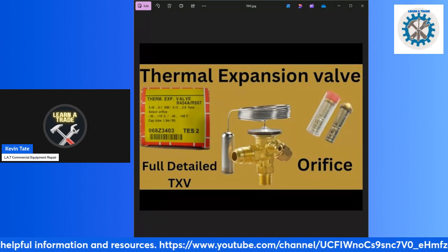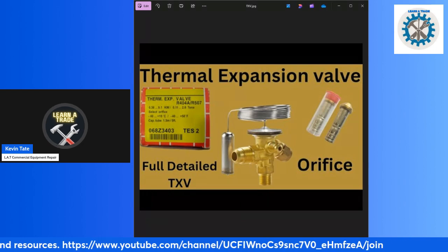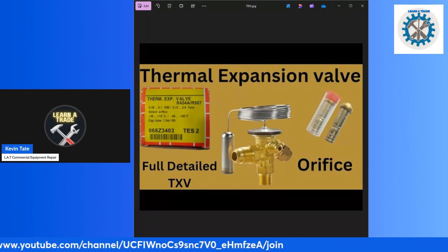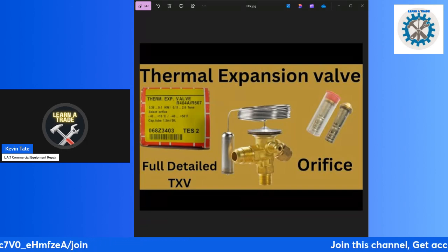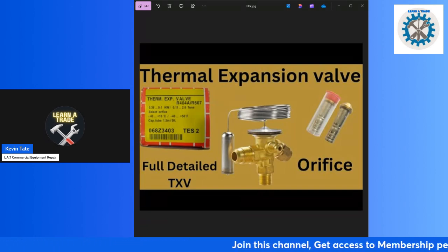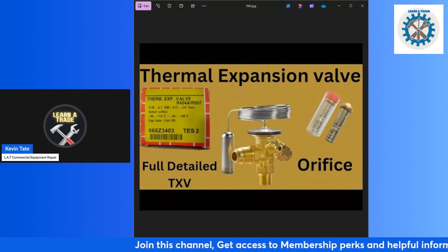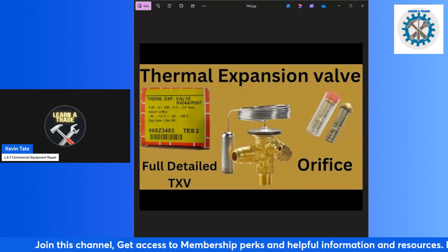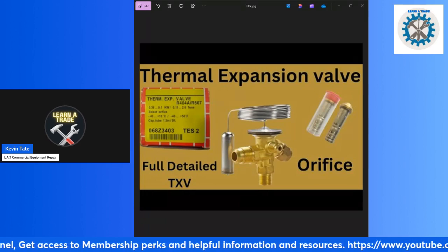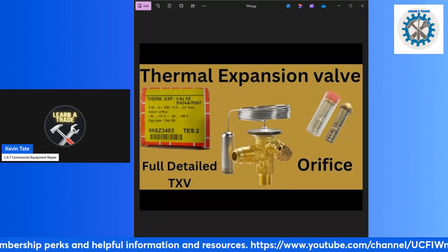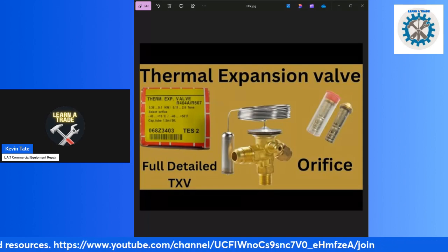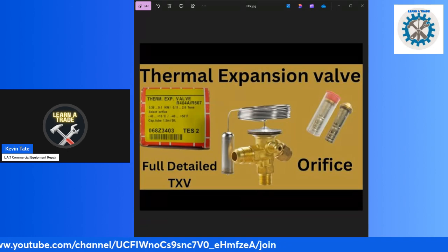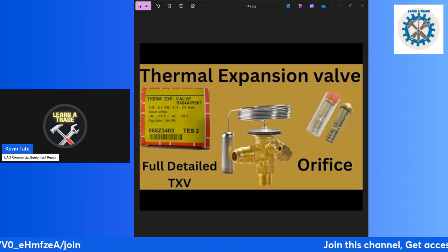Next, you want to find the proper extended capacity table in the catalog that you may be using. Now, this means if you're using a catalog online or in a manual that you may have, you want to find the proper extended capacity table in that catalog for the correct refrigerant at the proper evaporator temperature. Then locate the closest pressure drop column and find the nearest flow rate in tons to the evaporator tonnage.